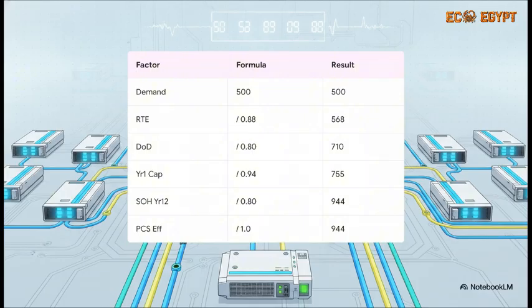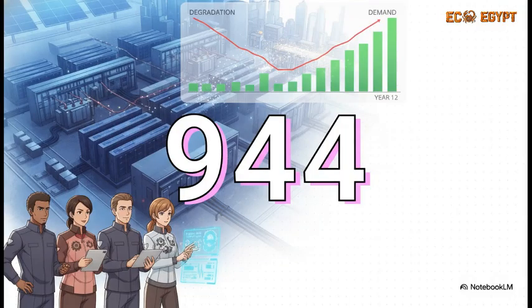To actually deliver those 500 kilowatt-hours, we first have to divide by our round-trip efficiency of 0.88. Boom, now we need 568. Then we divide by our depth of discharge limit of 0.80. Now we're up to 710. Next, we account for that initial first-year capacity drop of 0.94, getting us to 755. And finally, we divide by our projected state of health at year 12, which is 80%, or 0.80. If we factor in a perfect 1.0 power conversion system efficiency, the math leaves us at a final, way bigger number, 944 kilowatt hours. This perfectly illustrates why engineering is all about anticipating reality.